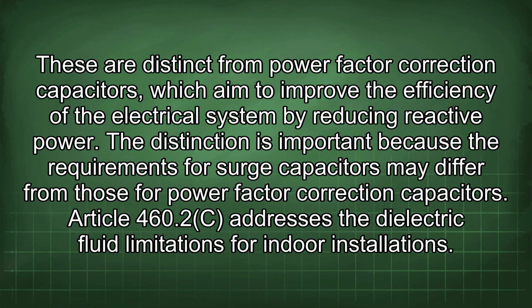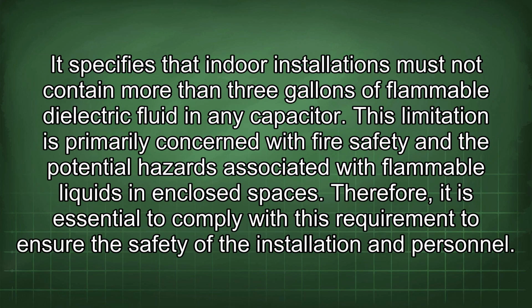Article 460.2c addresses the dielectric fluid limitations for indoor installations. It specifies that indoor installations must not contain more than 3 gallons of flammable dielectric fluid in any capacitor. This limitation is primarily concerned with fire safety and the potential hazards associated with flammable liquids in enclosed spaces. Therefore, it is essential to comply with this requirement to ensure the safety of the installation and personnel.